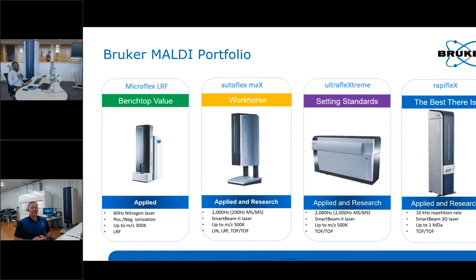The AutoFlex Max comes in different configurations: linear mode only, linear and reflectron mode, or TOF/TOF. If you choose linear mode, it's field upgradable — you can upgrade it over time to linear and reflectron TOF/TOF MS/MS capabilities.